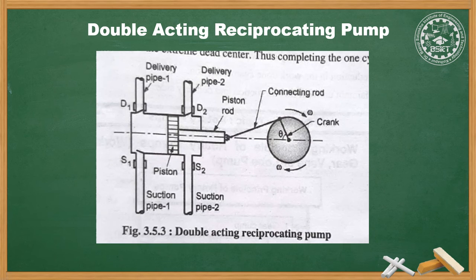The second is the double acting reciprocating pump. The disadvantage of the single acting pump — that discharge is intermittent — is eliminated here. This pump uses two suction and delivery pipes, one on each side, so suction and delivery strokes occur simultaneously. When the crank rotates from the inner dead center, a vacuum is created on the left side of the piston and liquid is sucked through suction valve S1. At the same time, liquid on the right side is pressurized, opening delivery valve D2 and pushing liquid out, while suction valve S2 remains closed.